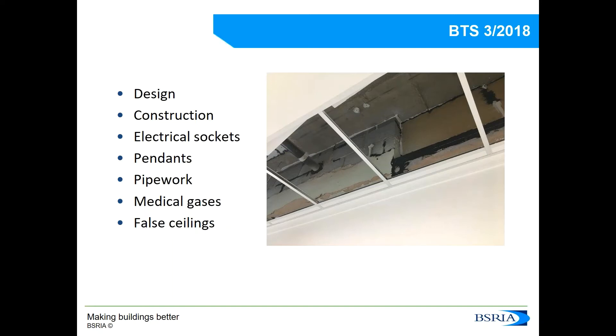In the standard, we give two examples of common isolation room designs. One is the design we are seeing today — with a lobby, patient's room, and en suite bathroom. The other is just the patient's room with en suite bathroom and no entrance lobby, which is another common design. The test only takes one day, but it is very important that the rooms are properly built and sealed to achieve the required air permeability on first test. If rooms have to be resealed and seals need to dry, we would have to return another day to retest. Ideally, airtightness should be considered from the design stage, as it is much easier to build with airtightness in mind than to correct it afterwards.